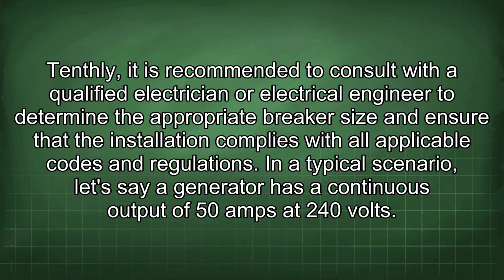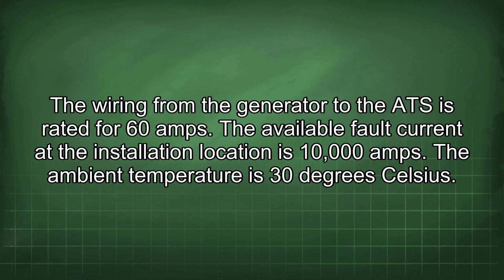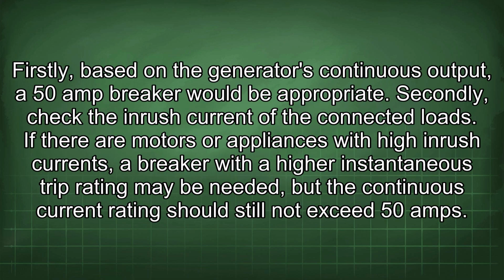In a typical scenario, let's say a generator has a continuous output of 50 amps at 240 volts. The wiring from the generator to the ATS is rated for 60 amps. The available fault current at the installation location is 10,000 amps. The ambient temperature is 30 degrees Celsius. Firstly, based on the generator's continuous output, a 50 amp breaker would be appropriate.